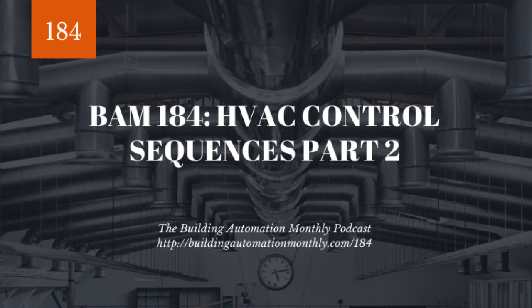Okay, so you've got this fan coil, right? And it's running and the cooling comes on. And then once it meets set point, the cooling will close down and the heating can open up. And if it goes below set point, right? And so that's how it controls it. And it's got a little bit of dead band between the cooling and the heating set point. So you have two separate set points.